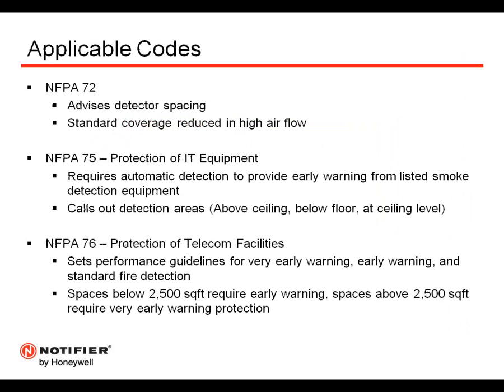Applicable codes for aspirating smoke detection. First of all, it's governed by NFPA 72, so in standard smoke detection mode, the sample ports must be spaced as any spot detector would be spaced. NFPA 72 also prescribes standard coverage in high airflow environments. The first NFPA code that really starts getting into aspirating smoke detection would be NFPA 75, which details the protection of IT equipment. Now, this is the first that calls out early warning smoke detection, and it also calls out areas in the environment that would need to be protected, such as at the ceiling level, above the ceiling, or below the floor if there is a raised floor area.